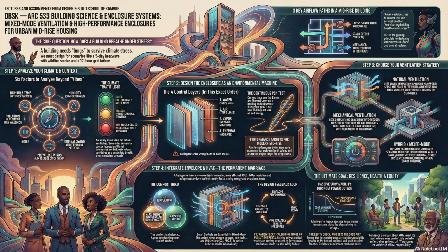And test 3 is the most complex. Test 3 is the logic. Under what specific conditions, temperature, time, and pollution levels is each mode allowed to operate? If you can't answer that with precise logic, like natural mode is permitted when outdoor temp is between 65 and 78 and PM2.5 is below 15, then your design is just arbitrary. The building won't know how to breathe when conditions change.